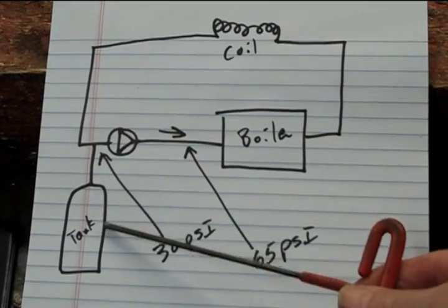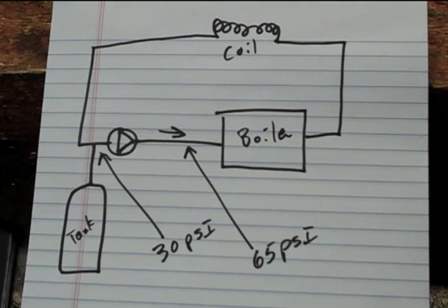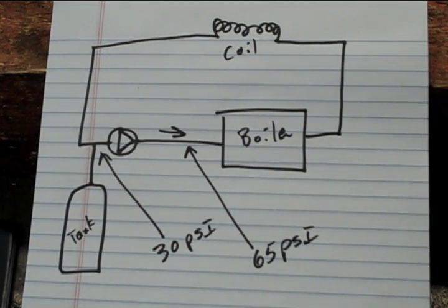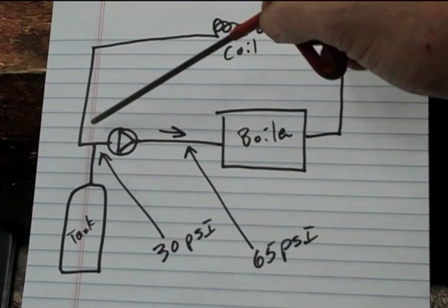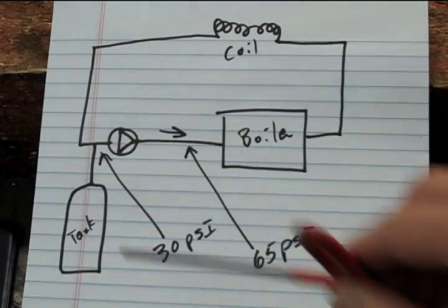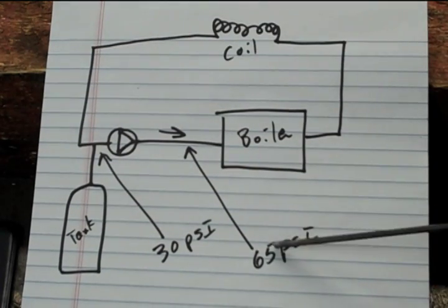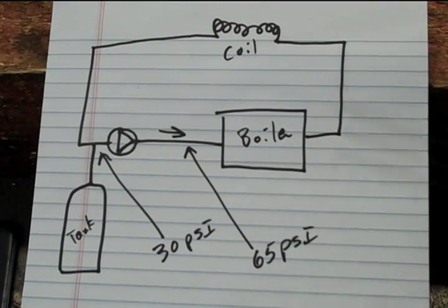Before you attach your tank to the system it needs to be pre-charged to the pressure of the system at the attachment point. On this one where the pressure is 30 psi on the suction side of the pump, that's where we're attaching, so we're going to pre-charge the tank to 30 psi before we attach it. If we were attaching it on the discharge side of the pump where there's 65 pounds of pressure, we would pre-charge it to 65 pounds.